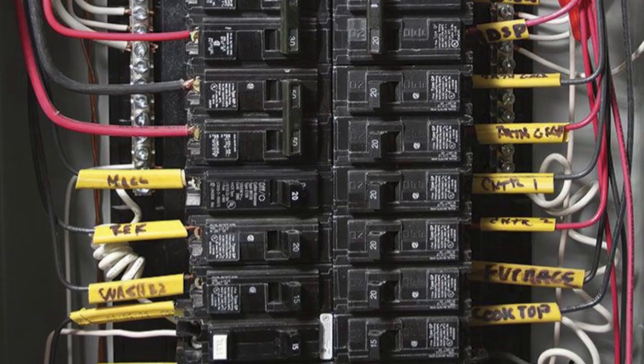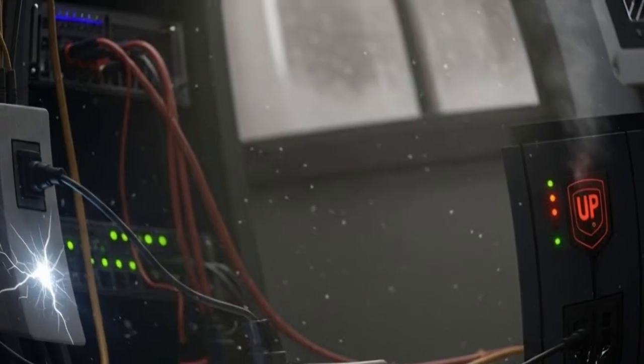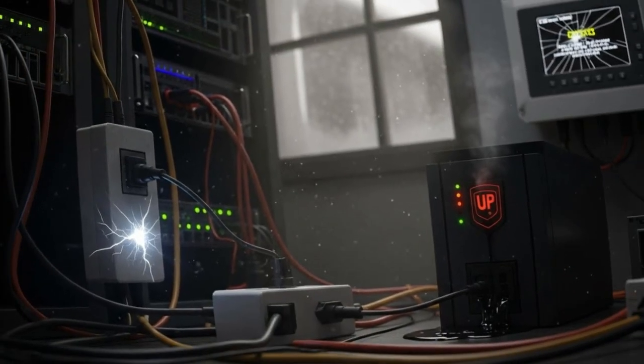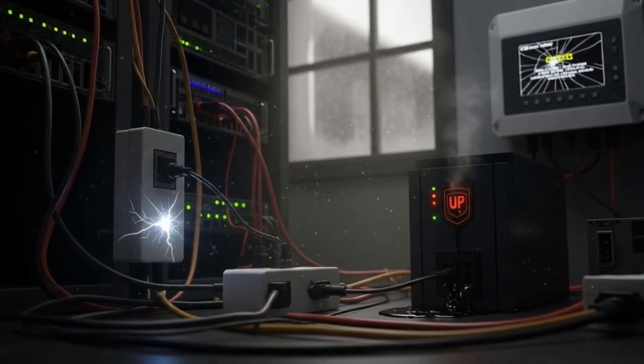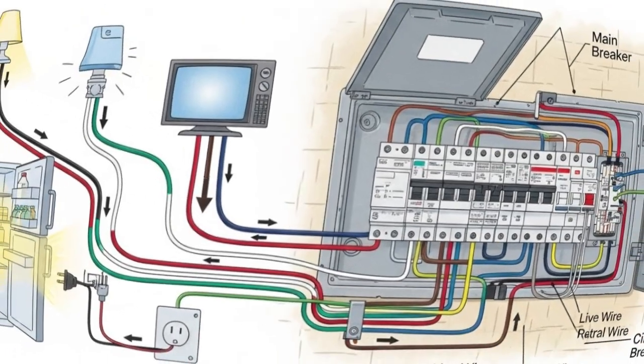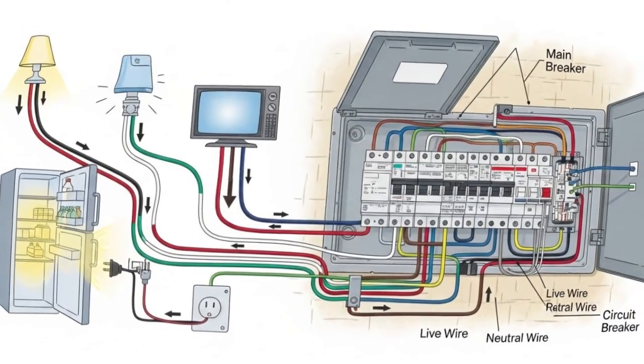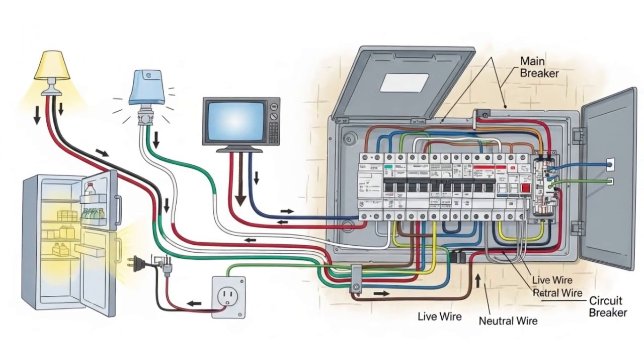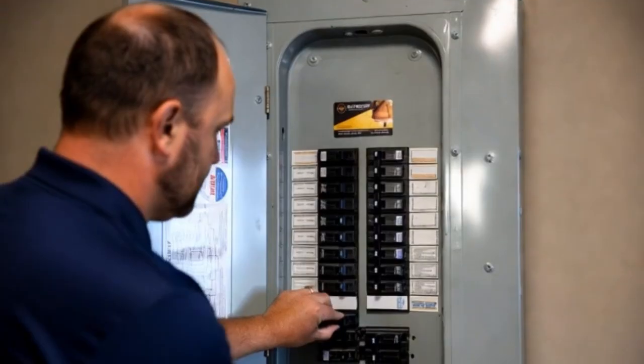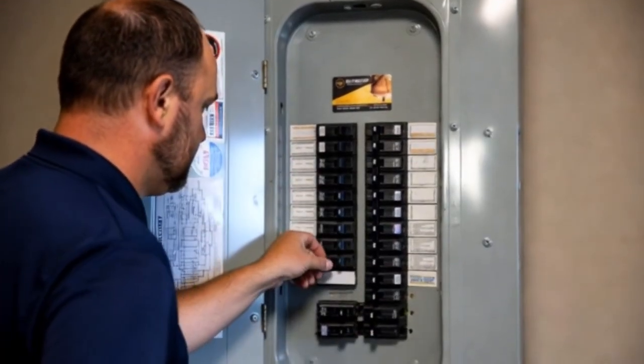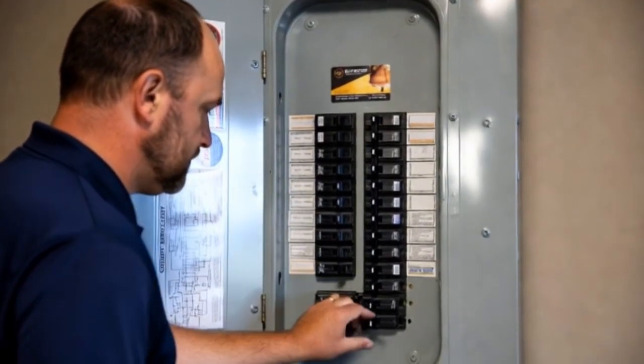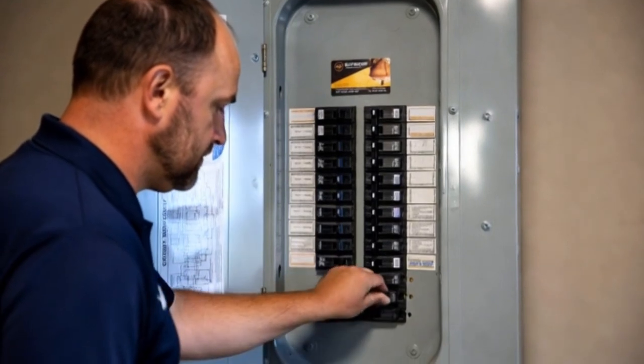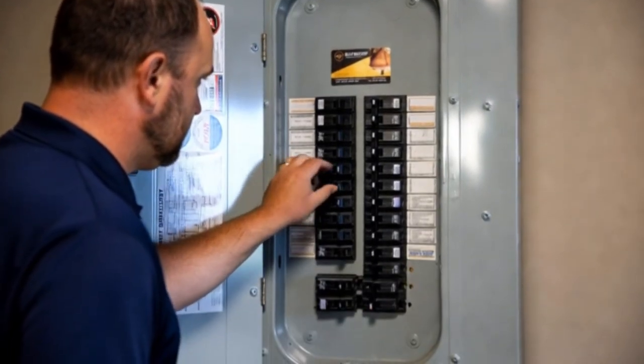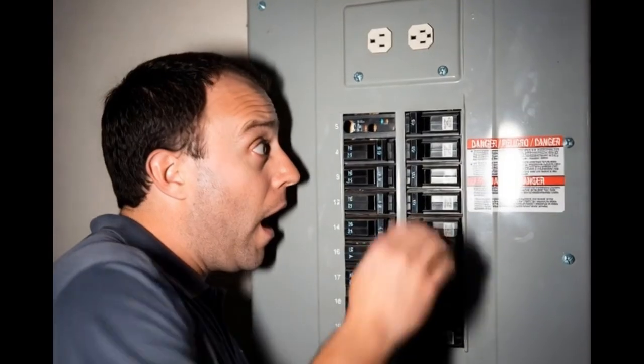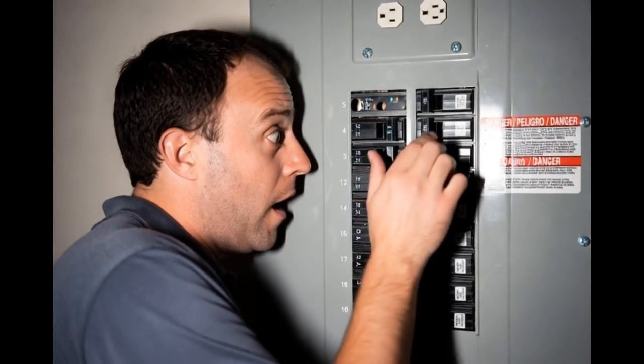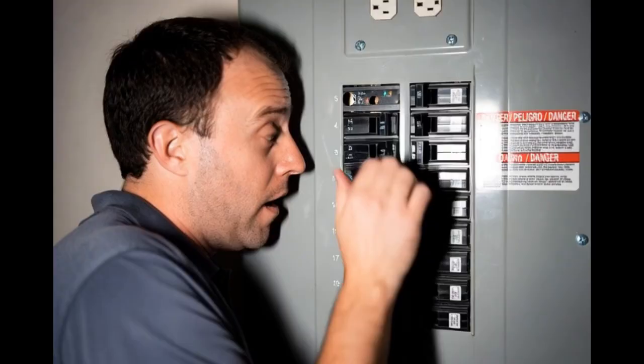Backfed current can also come from faulty surge protectors, failing UPS battery backup units, and malfunctioning solar inverters. Any device that interfaces with your electrical system has the potential to send current back upstream when it fails. If your main breaker only trips at certain times, when the air conditioner kicks on, when the refrigerator cycles, or when a specific appliance runs, a backfeeding appliance may be the root cause. Identifying the faulty device requires isolating circuits one by one until the problem disappears.